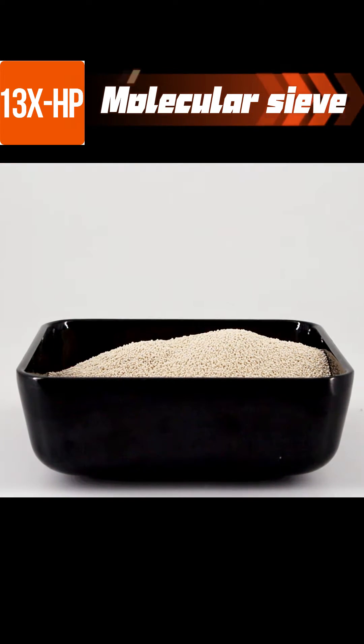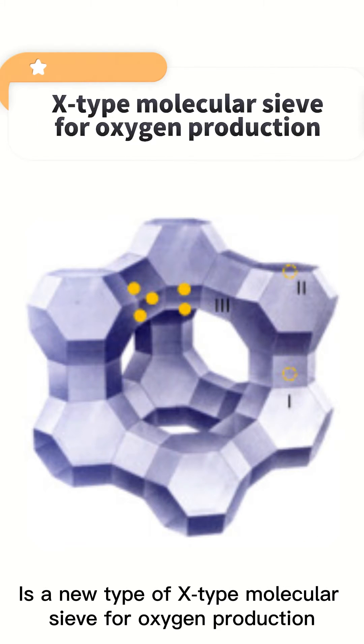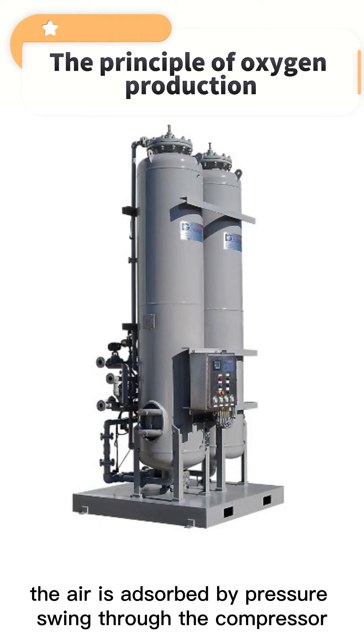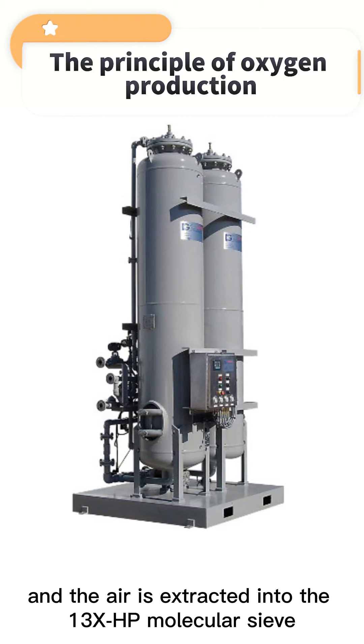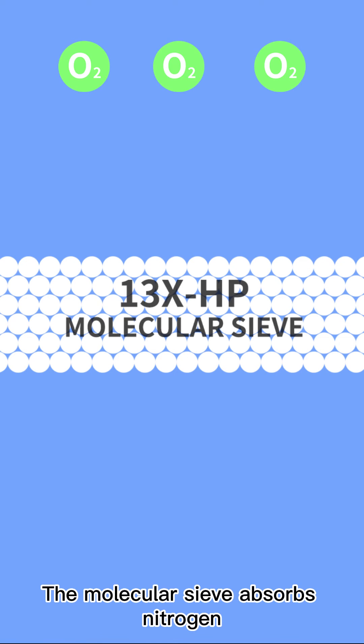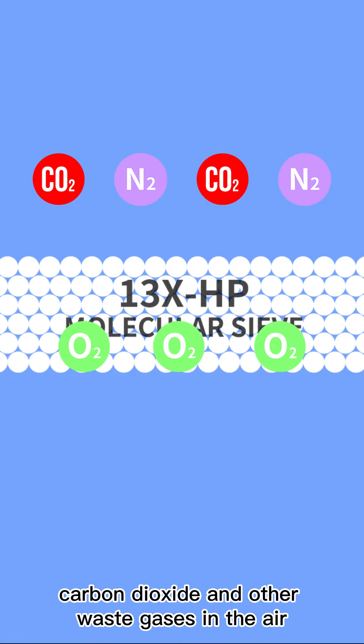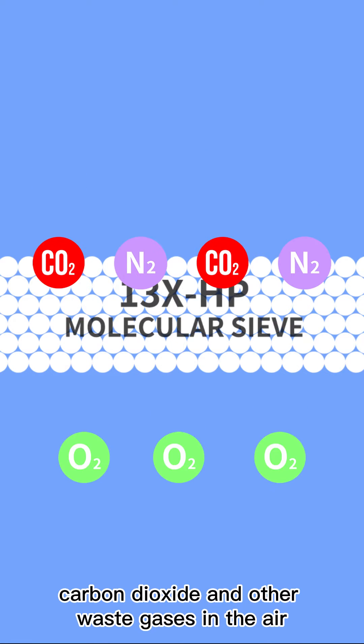13X-HP molecular sieve is a new type of X-type molecular sieve for oxygen production. The principle of oxygen production is: the air is adsorbed by pressure swing through the compressor, and the air is extracted into the 13X-HP molecular sieve. The molecular sieve absorbs nitrogen, carbon dioxide, and other waste gases in the air.